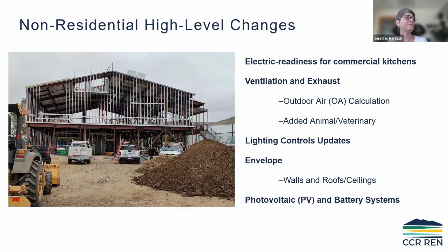And then the second question, which I'll just reference and answer so we can keep moving. Nick Holt brought up a real issue that we've been finding too. He referenced a high altitude, heating dominated, cold climate. They're primarily heating the spaces, and he's seeing additional heat required when doing load calcs and sizing for HVAC systems, because those heat pump water heaters are heating the water and the unit's dumping cold air into the space. Depending on where that unit is located and where that exhaust air is going, there's additional cooling being added to your home. And if your home wants heat, your HVAC system designer or contractor didn't factor in that additional cooling being introduced, and you have to upsize and account for it.